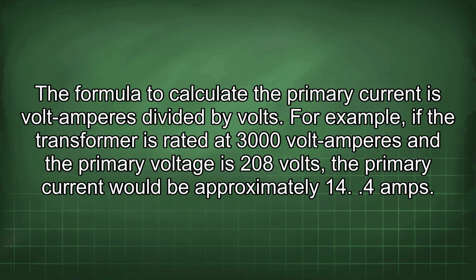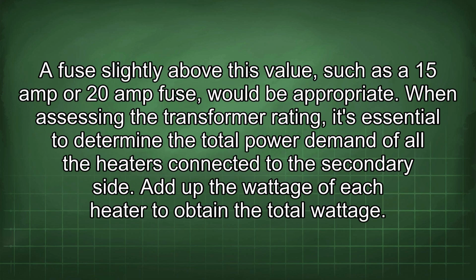The formula to calculate the primary current is volt-amperes divided by volts. For example, if the transformer is rated at 3000 volt-amperes and the primary voltage is 208 volts, the primary current would be approximately 14.4 amps. A fuse slightly above this value, such as a 15 amp or 20 amp fuse, would be appropriate.